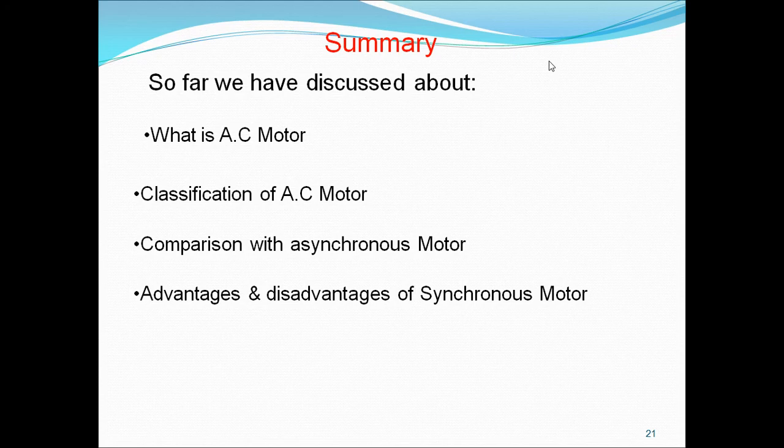When they increase the excitation, the synchronous motor starts running at leading. So if you combine lagging and leading, the power factor will improve. Suppose it reduces to 0.7, when we connect the synchronous motor, it rises to 0.8. Likewise, it can be used to improve the power factor for industries.